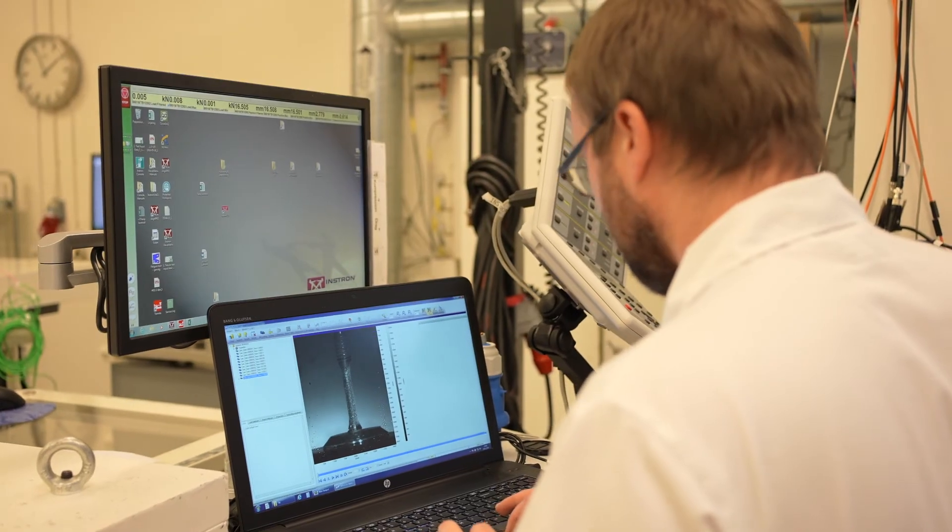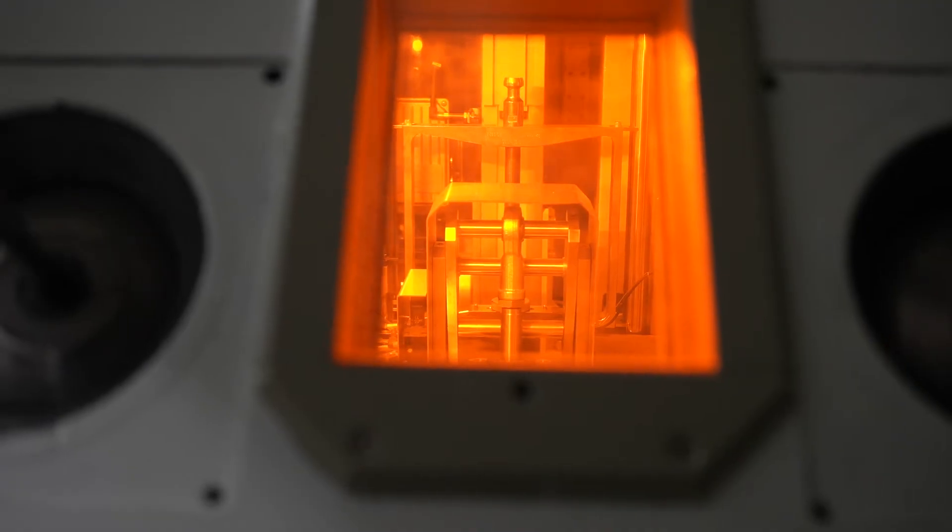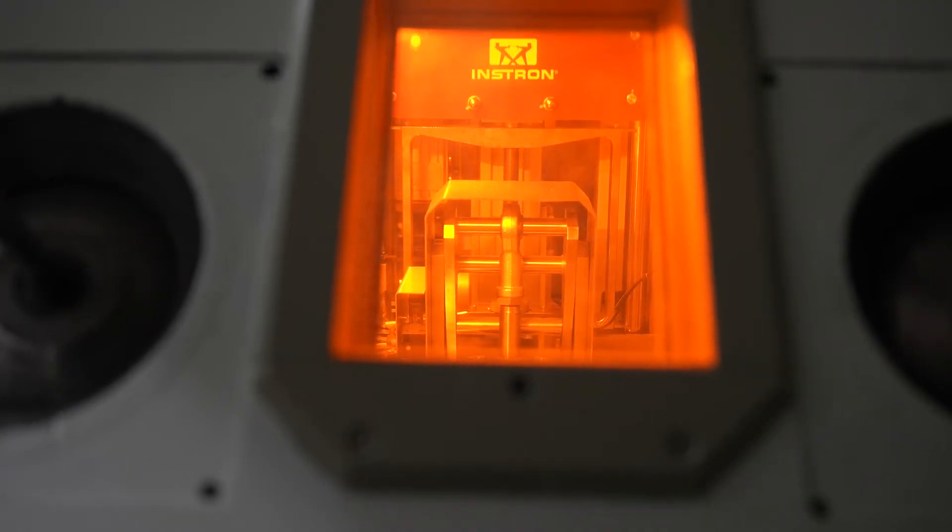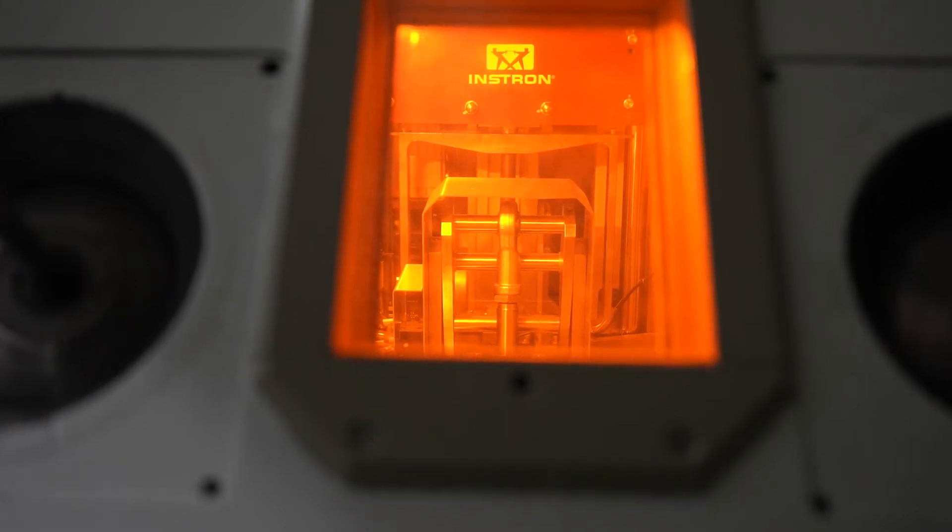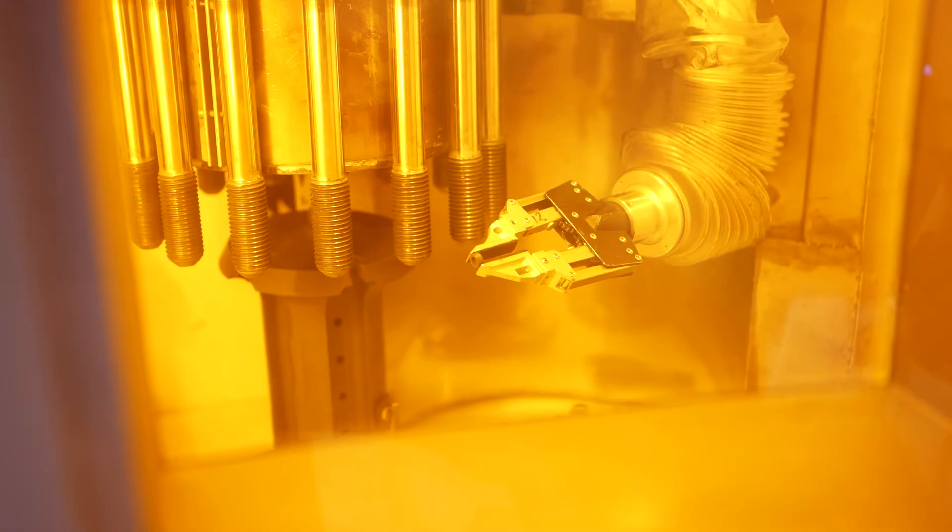Creep tests can be performed at temperatures exceeding 600 degrees Celsius for long periods of time. For fatigue initiation and propagation, fracture toughness, and tensile testing, the load cells, grips, and adapters of the testing machines are interchangeable to enable tests on specimens with various sizes and geometries.